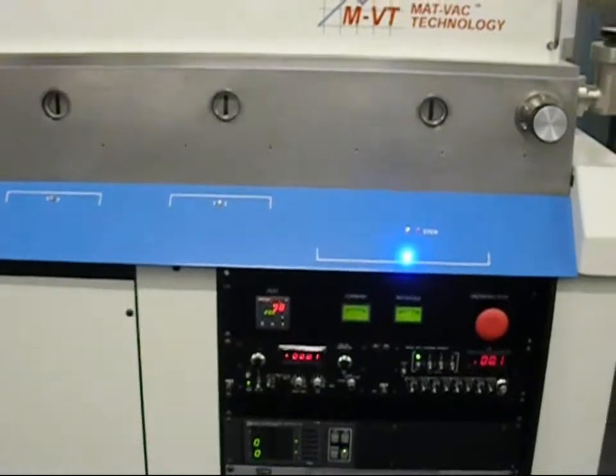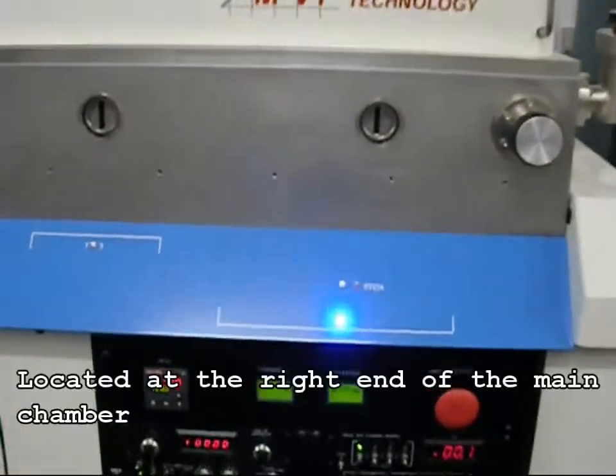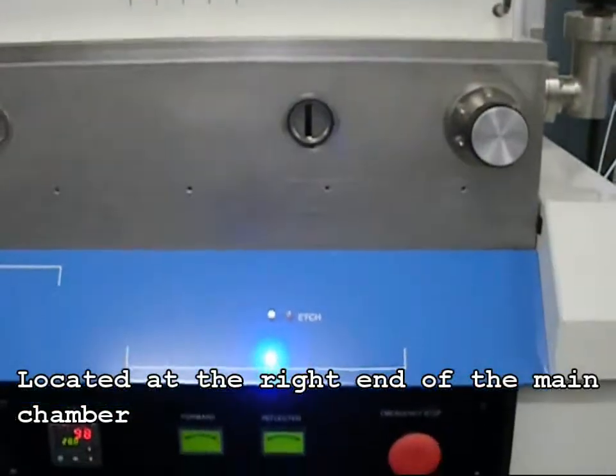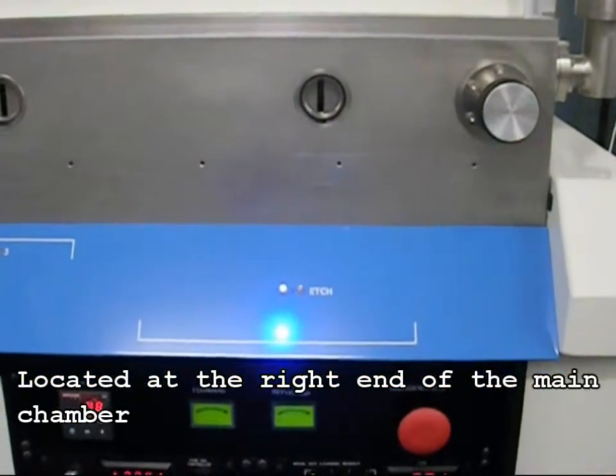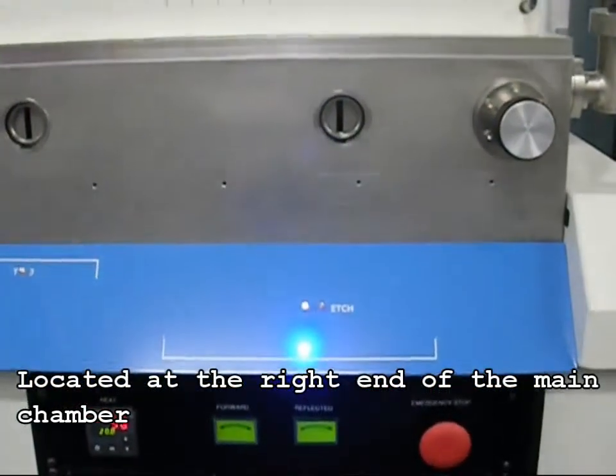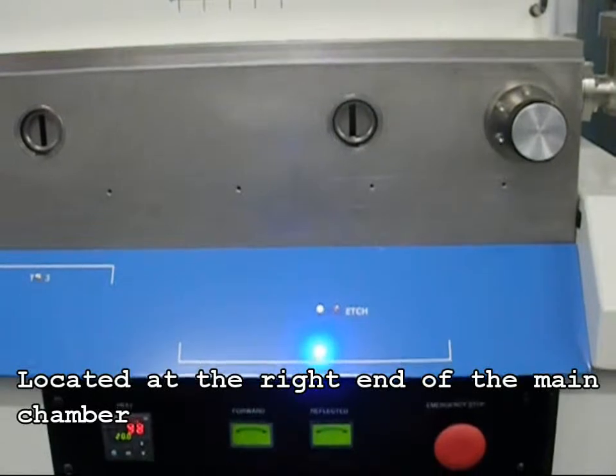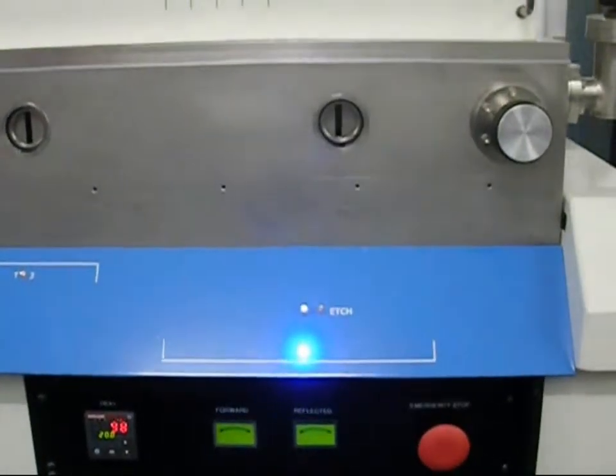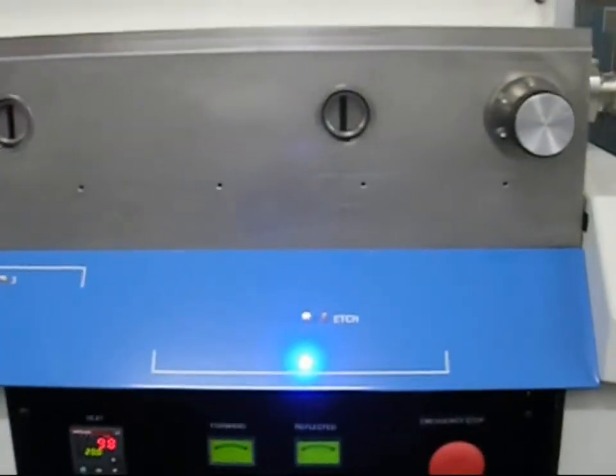Typically, an initial substrate pre-cleaning step is performed by a RF sputter etch process on the RF etch platform. The 2-position RF etch platform will rise to the upper position, process gas will turn on, and RF power will be supplied to the etch platform and the substrate pallet. Plasma ignition is accomplished automatically by MAT-VAC technology special software without the need of a glow start plasma igniter.